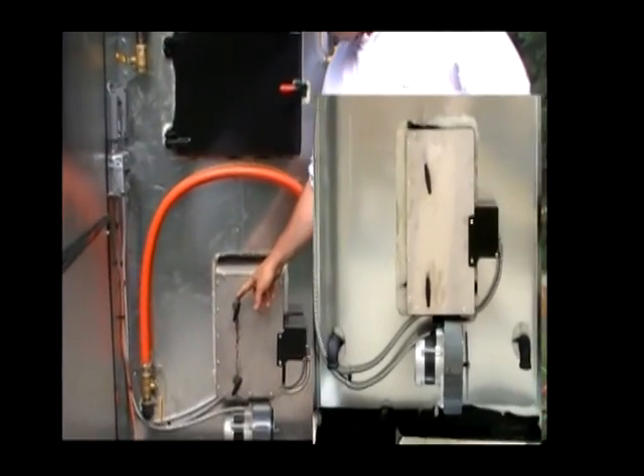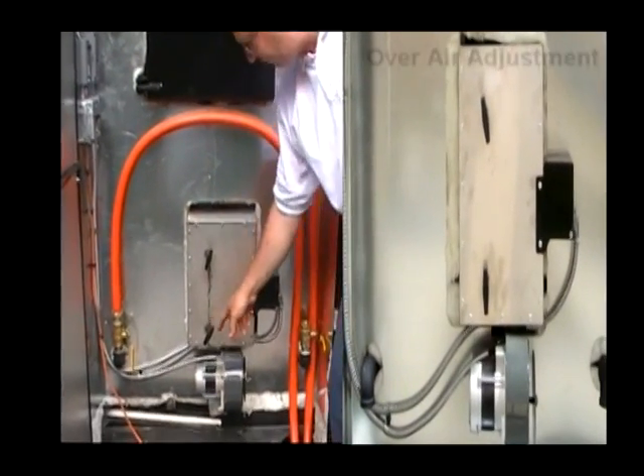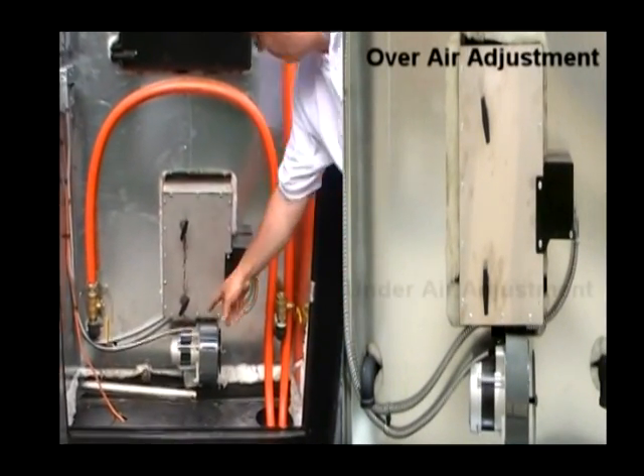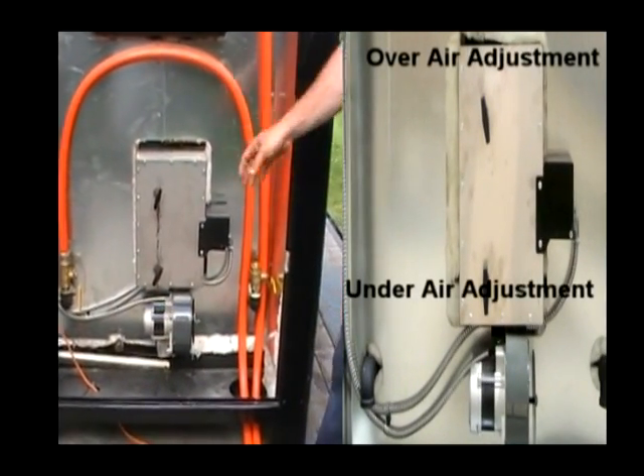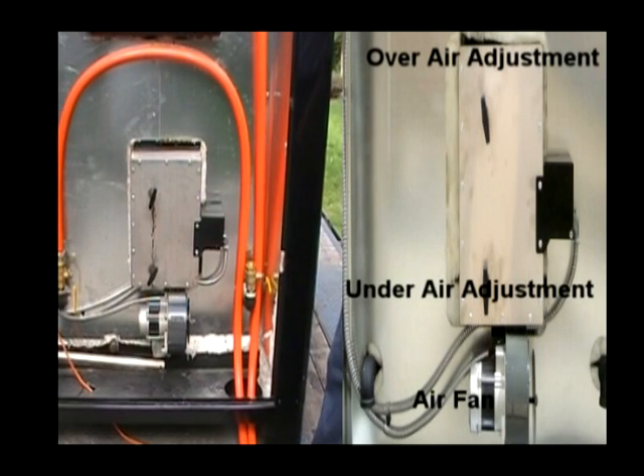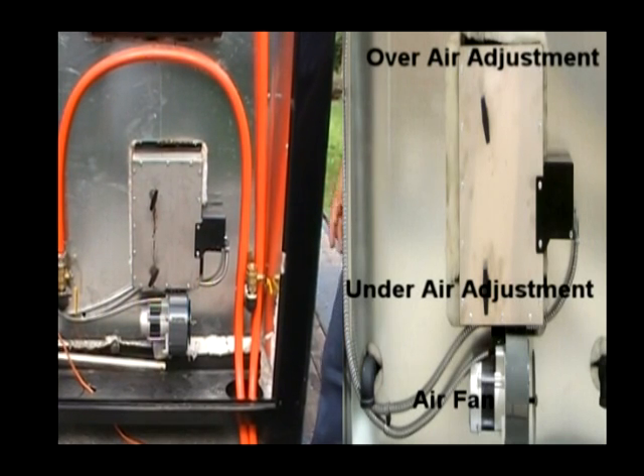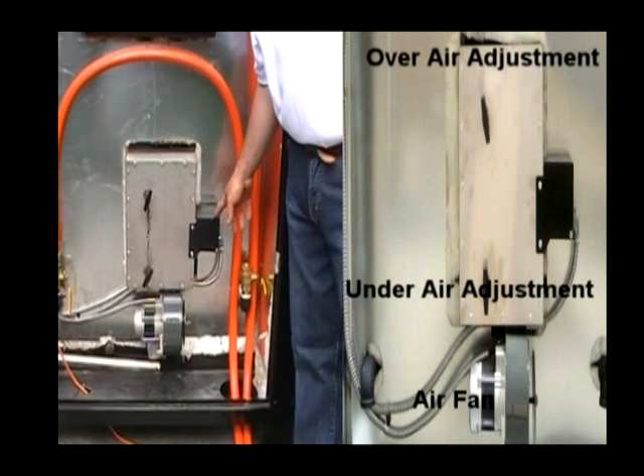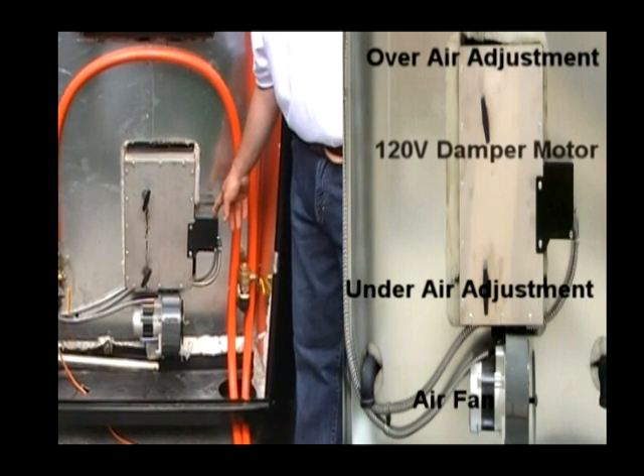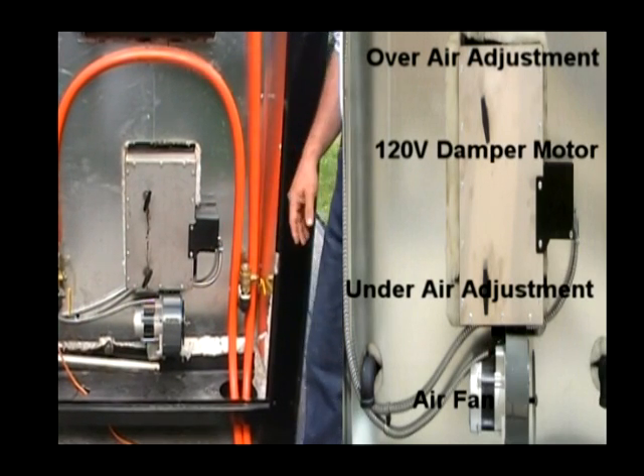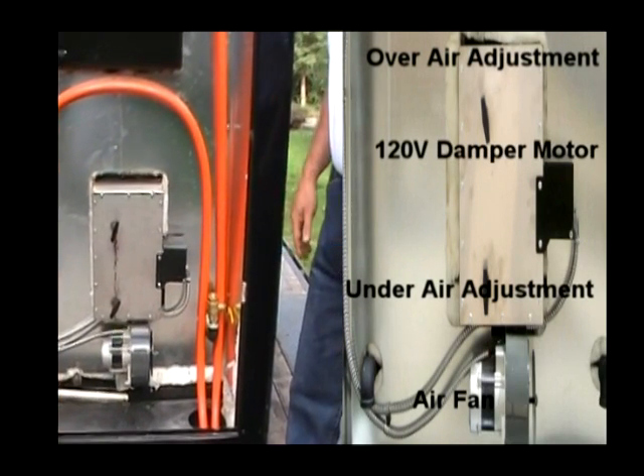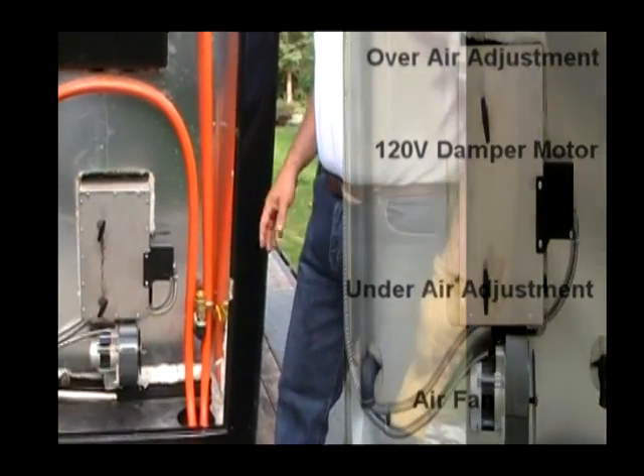Our air box has adjustable air above the fire and below the fire. The fan is a fully enclosed ball bearing fan, capacitor started, thermally protected, very good quality ball bearing fan. Fully enclosed. We have a 120 volt motor to shut off the air positively with a gasketed shut off in the air box, so we get total shut off of our air.